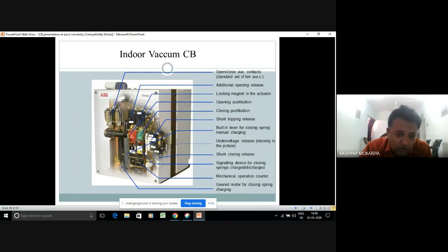In your studies, you are studying that we have to see the mechanical operation of the breaker. So what they are doing is, after manufacturing, they want to test that the breaker assemblies are joined perfectly. So I will test my breakers, suppose 1,000 times on off mechanism, and I will see that all the parts, all the washers, all the springs are in intact position. Nothing has been damaged in the breaker. So all these industrial tests are classified into type tests, routine tests, then special development tests, and commissioning tests.